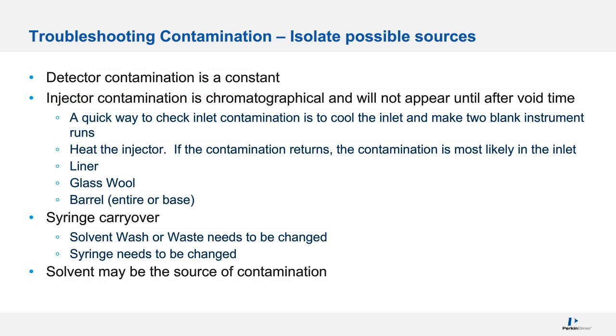Troubleshooting contamination. This is where isolating the parts is so helpful. Detector contamination is constant. It starts from time 0. Cap the detector, light it if it's an FID, if it's a mass spec. If the problem goes away, you right away know it's not your detector. Inlet contamination is chromatographical because usually the stuff condenses at the low temperature, and then when you bring up the temperature, that's when it's seen.